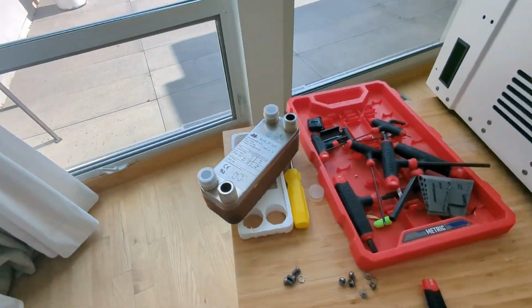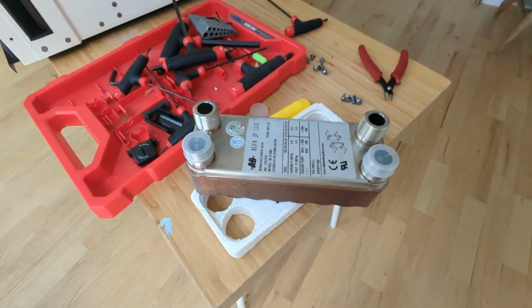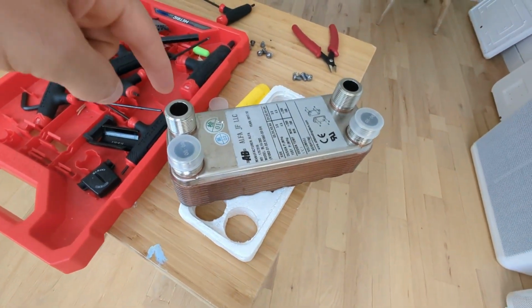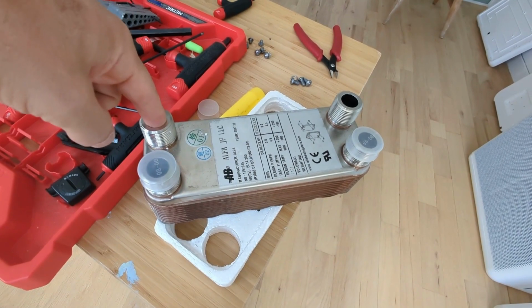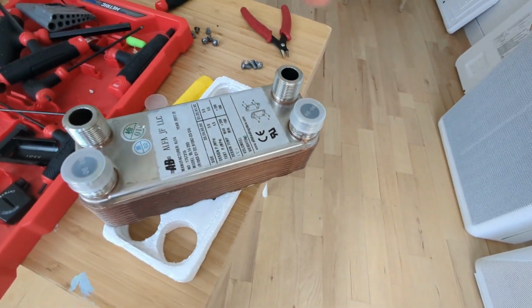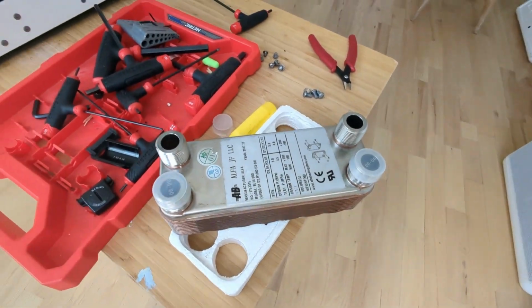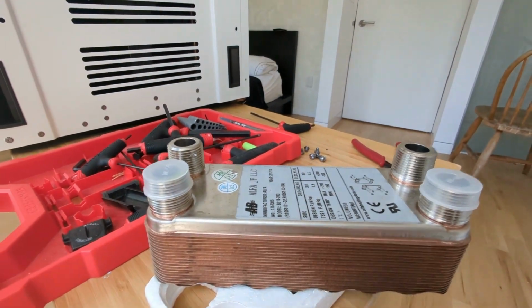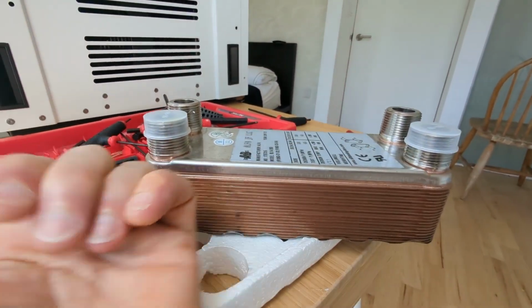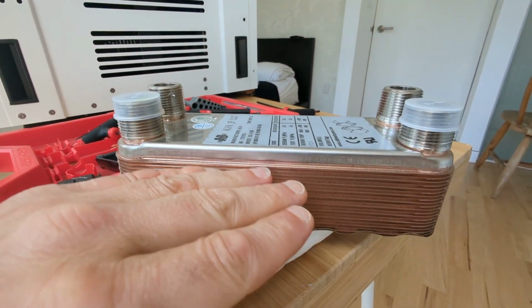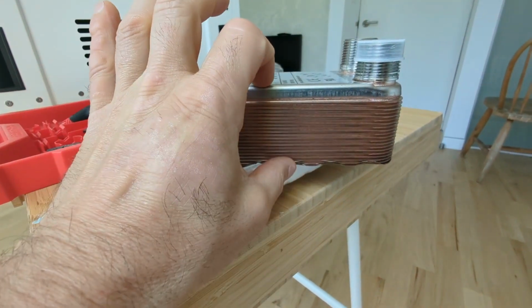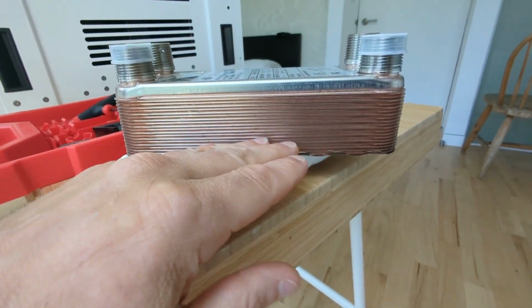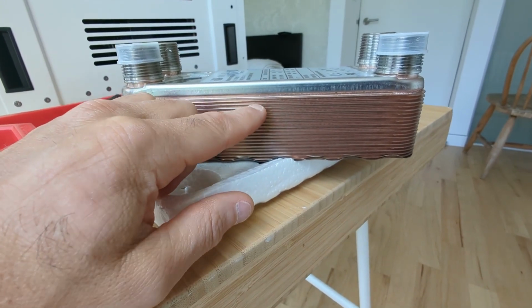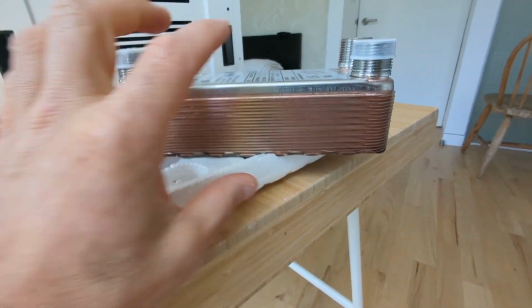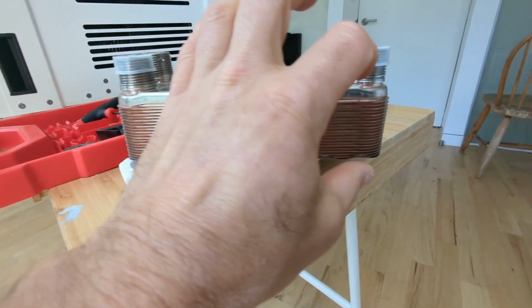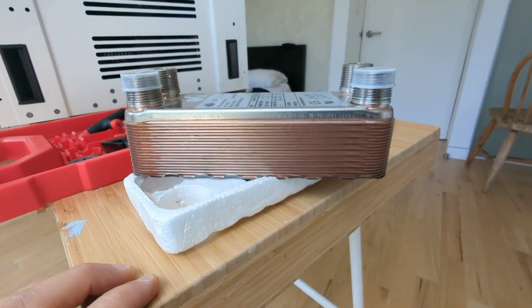I have a smaller one here, and the way it works is you'd have, say, refrigerant going in here and coming out here, and then coolant going in here and coming out here. And so the refrigerant is flowing one way and the coolant is flowing the other way. And if you see, this is a stack of plates. Every other set of plates, one set is refrigerant, then the next is coolant, then refrigerant, then coolant. So you have a huge amount of surface area for them to trade heat.